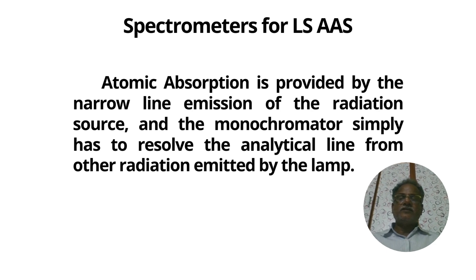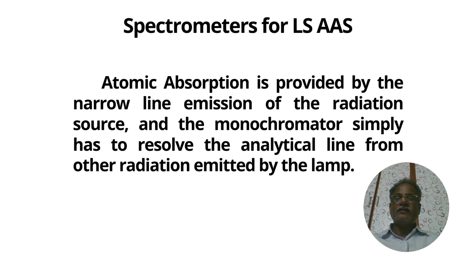The spectrometers for line-source atomic absorption spectroscopy are provided with a narrow line emission of the radiation source, passing between 0.2 and 2 nanometers — that is, a low-resolution monochromator. A monochromator filters the radiation at a desired wavelength from polychromatic radiation.